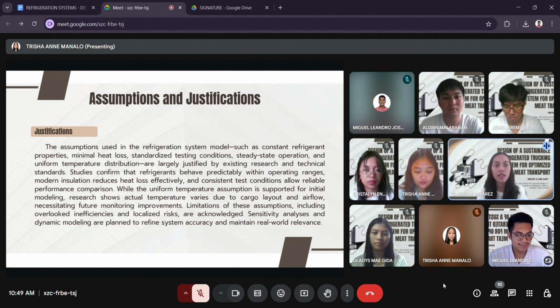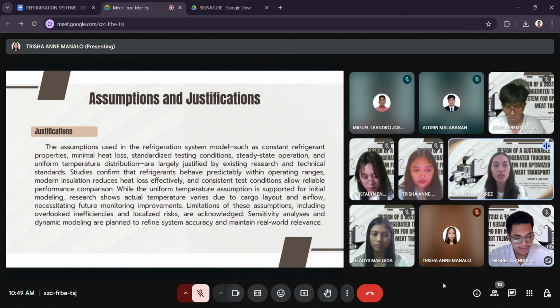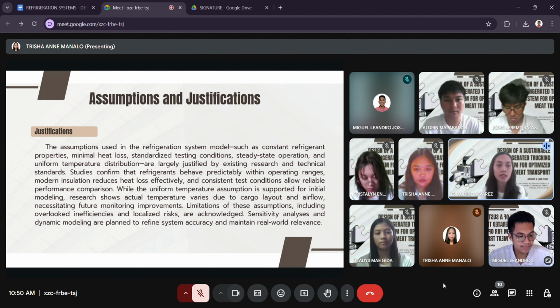For the justifications, the assumptions used in the refrigeration system model, such as constant refrigerant properties, minimal heat loss, standardized testing conditions, steady-state operation, and uniform temperature distribution, are largely justified by existing research and technical standards. Studies confirm that refrigerants behave predictably within operating ranges. Modern insulation reduces heat loss effectively, and consistent test conditions allow reliable performance comparison. While the uniform temperature assumption is supported for initial modeling, research shows actual temperature varies due to cargo layout and airflow, necessitating future monitoring improvements. Limitations of these assumptions, including overlooked inefficiencies and localized risks, are acknowledged. Sensitivity analysis and dynamic modeling are planned to refine system accuracy and maintain real-world relevance. Next slide po.